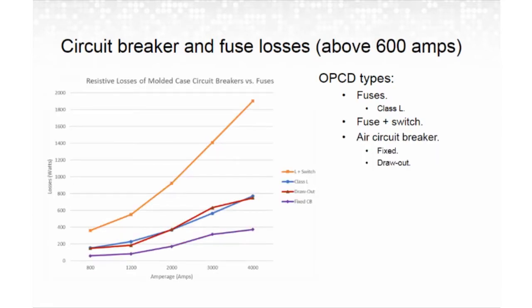So this next slide, while looking similar to before, is for circuit breakers and fuses rated above 600 amps. And we can see that the type of breaker chosen can affect the power dissipated by the breaker. The orange line at top is a switch with a class L fuse. The class L fuse contribution is shown in blue all by itself. The red line represents a drawout circuit breaker, and it coincidentally follows the power loss of the class L fuse.